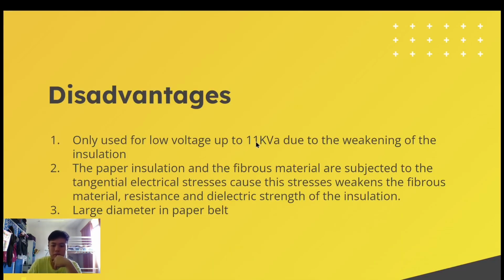Now I would like to present the disadvantages of the belted cable. So basically there are three main disadvantages. The first one is that belted cable can only be used for low voltage, up to 11 kV, due to the weakening of the insulation. So when the voltage is bigger than 11 kV, the belted cable is not suitable to use.